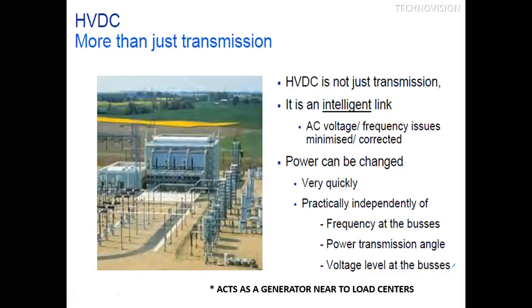Suppose there is an HVDC link with a capacity of 1500 megawatt from Chandrapur to Padge. Chandrapur is at a distance of 752 kilometers from Padge. When power is transmitted from Chandrapur to Padge, that 1500 megawatt power, with a loss of only 1 to 1.5%, you will get at the Padge station, that is, Padge 400 kV. So the system behaves as if I have connected 3 generators of 500 megawatt at Padge itself. That means the system acts as a generator near the load centers.